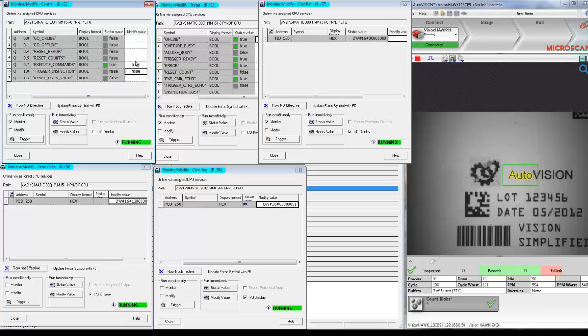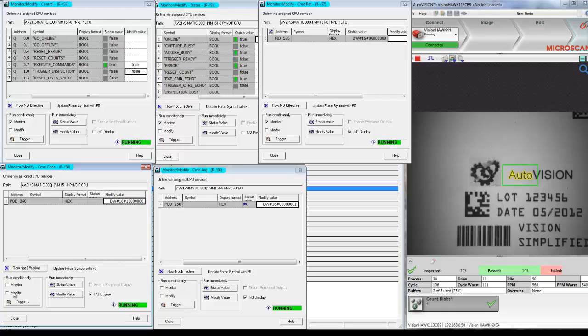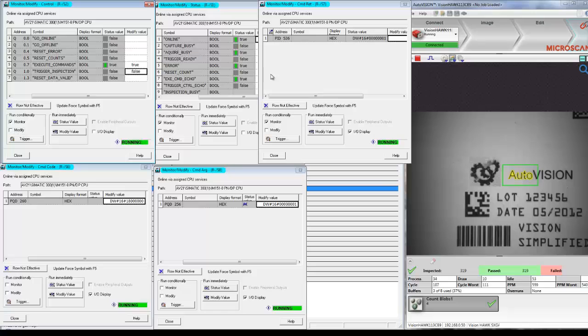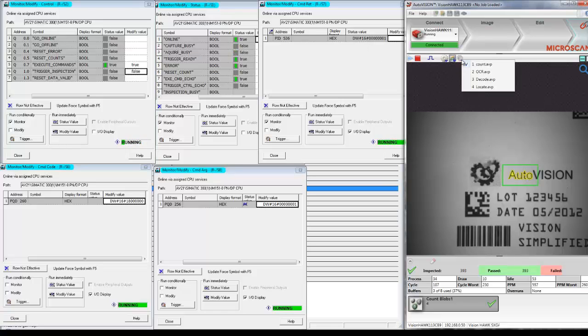The last thing to show you is how to query what job is currently on the camera. The command code for that is 18. Update the fields. Again, I have to execute the command, so I first have to set it back to zero and then to one again, and update it. In the command return field, you can now see which job is running — and that's job number one. And this is how to change a job using Profinet IO. I'll see you in the next video.